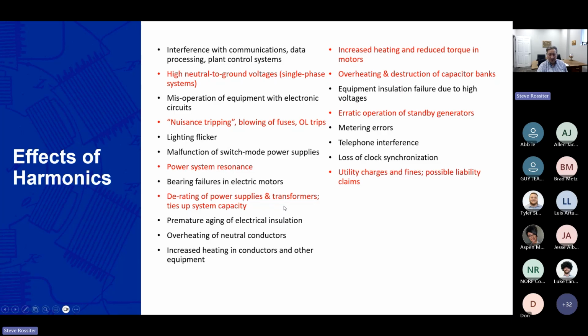De-rating of transformers, you've probably heard of K-rated transformers, simply a transformer that's rated to handle so much nonlinear load or distortion. Erratic operation of standby generators, like I mentioned, a generator can only handle so much distortion before it's not going to be able to regulate properly. And then ultimately, utility fines and charges.